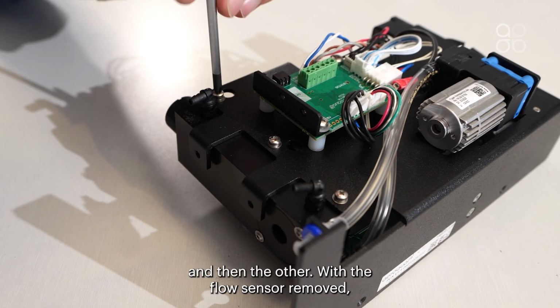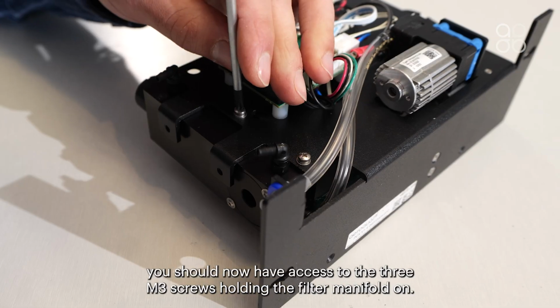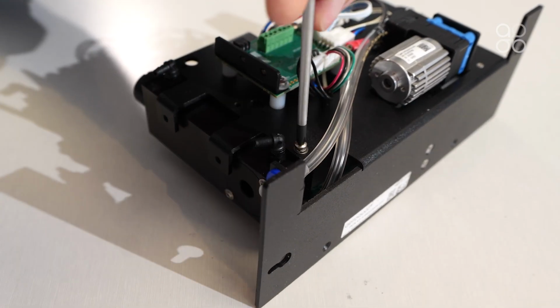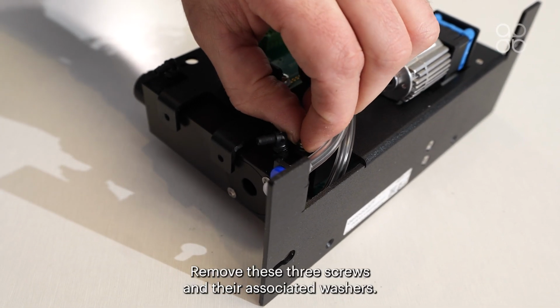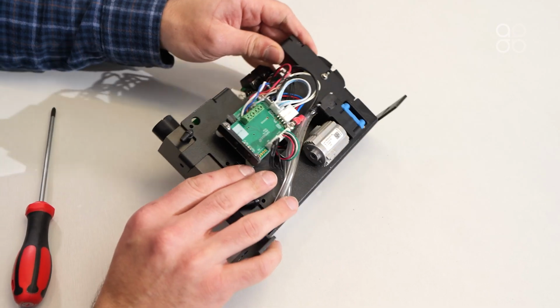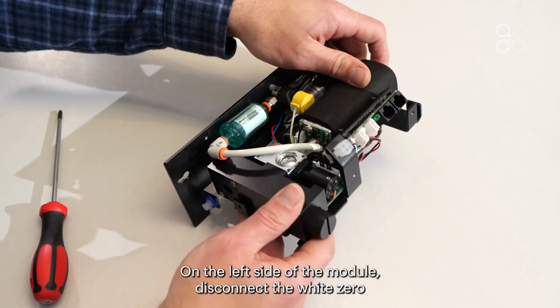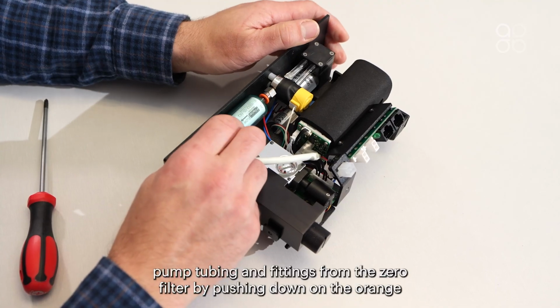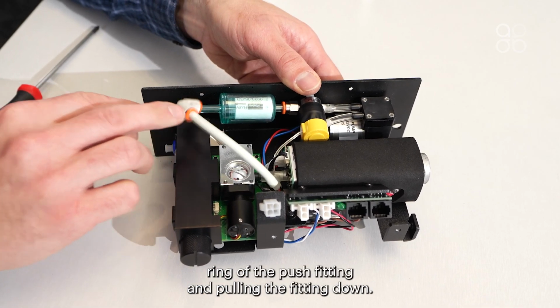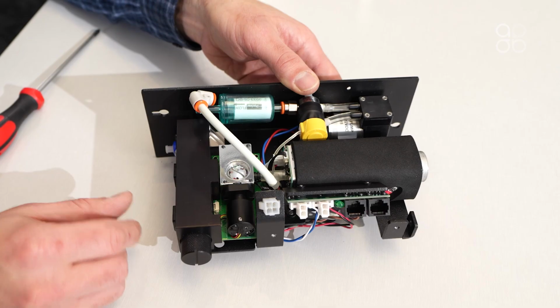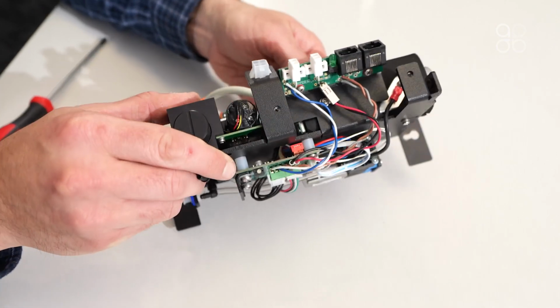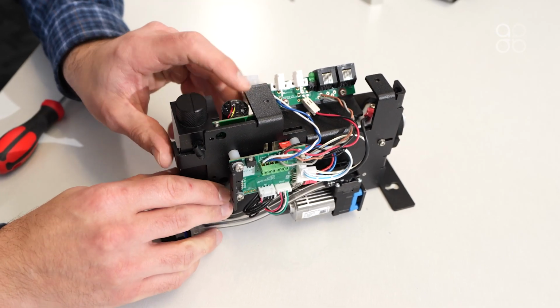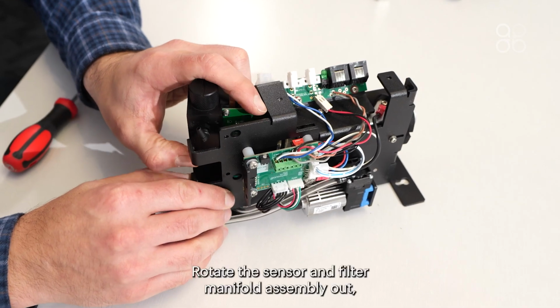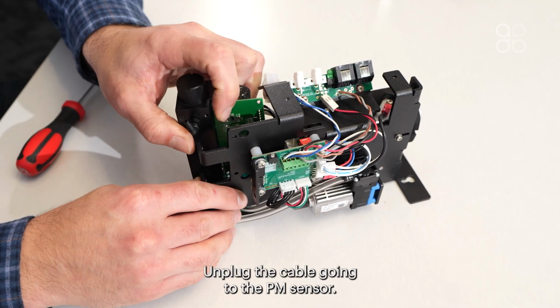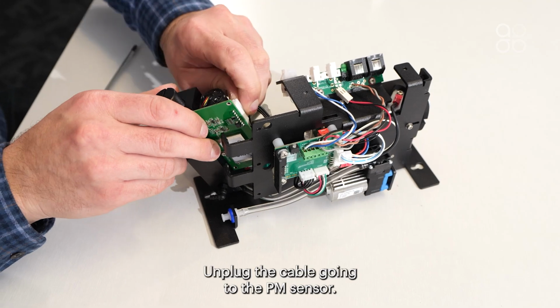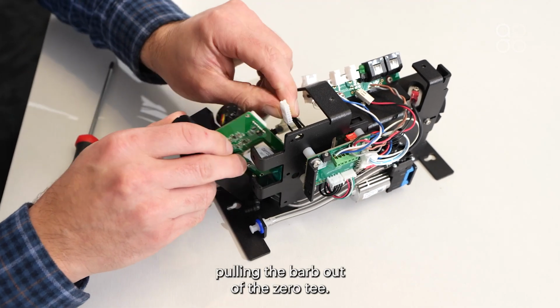With the flow sensor removed, you should now have access to the 3 M3 screws holding the filter manifold on. Remove these 3 screws and their associated washers. On the left side of the module, disconnect the white zero pump tubing and fitting from the zero filter by pushing down on the orange ring of the push fitting and pulling the fitting down. Rotate the sensor and filter manifold assembly out. Unplug the cable going to the PM sensor, pulling the barb out of the zero tee.